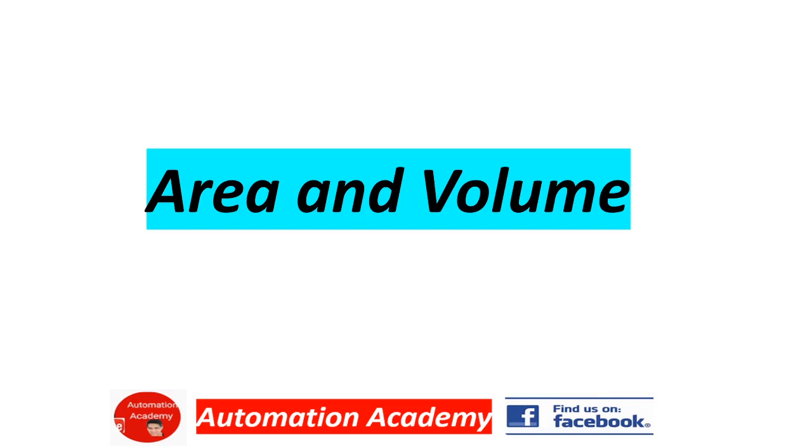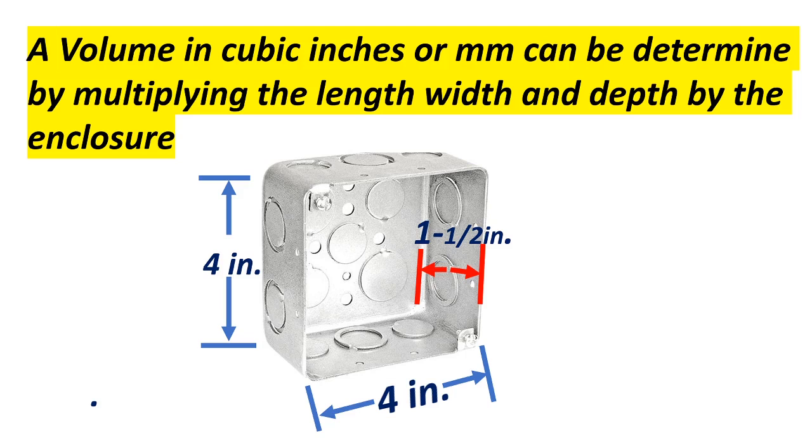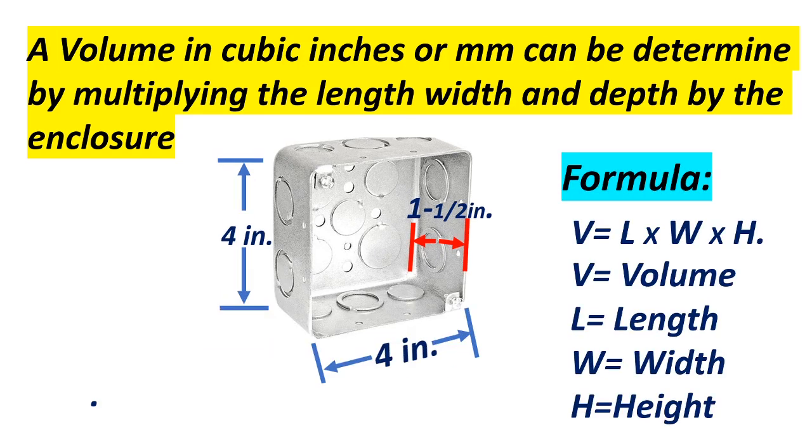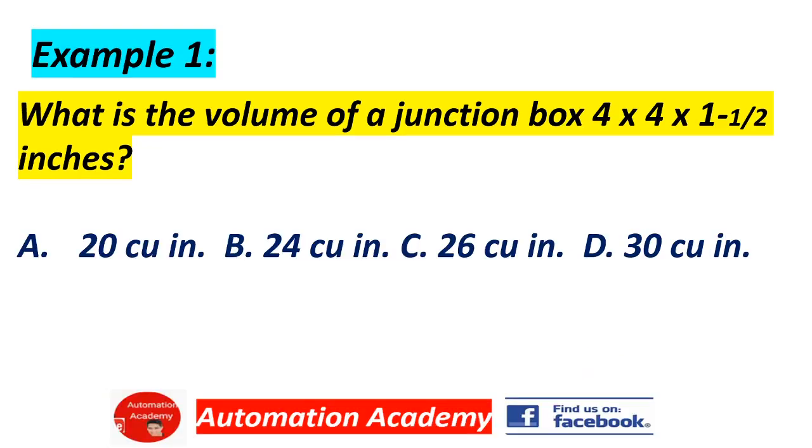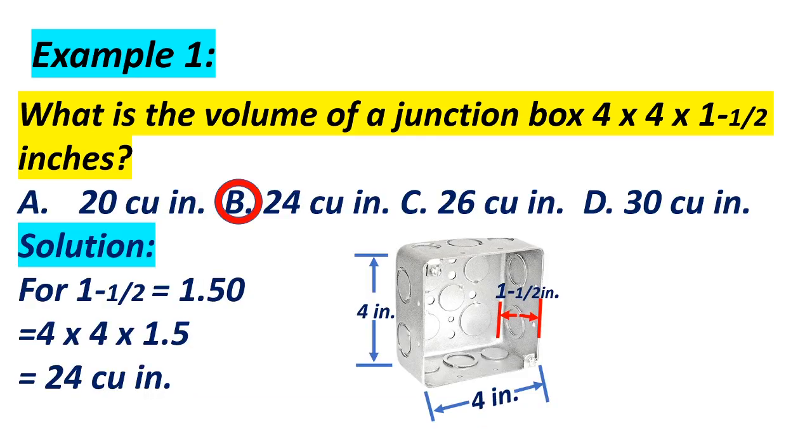Our next topic is area and volume. A volume in cubic inches or millimeters can be determined by multiplying the length, width, and depth of the enclosure. We have here an example of a utility box. The length is 4 inches, the width is 4 inches, and the depth is 1.5 inches. The formula for volume: V = L × W × H. Example number 1: What is the volume of a junction box 4 by 4 by 1.5 or 1 and 1/2? A. 20 cubic inches, B. 24 cubic inches, C. 26 cubic inches, D. 30 cubic inches. Solution: 1 and 1/2 equals 1.5, so 4 × 4 × 1.5 equals 24 cubic inches.